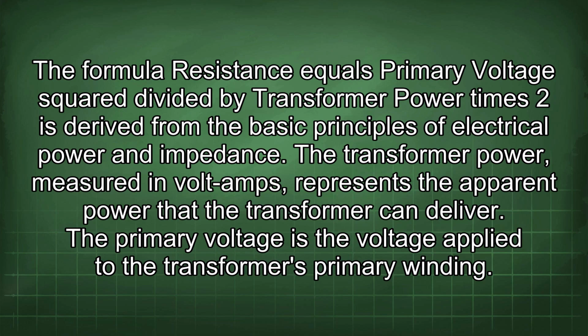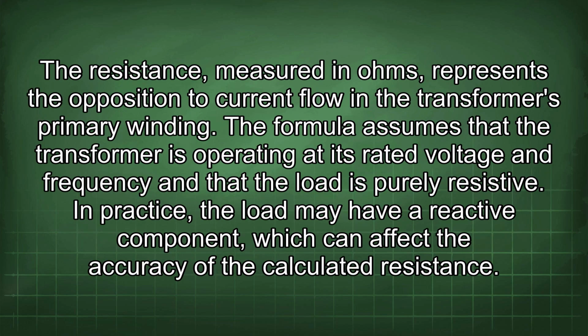The formula resistance equals primary voltage squared divided by transformer power times 2 is derived from the basic principles of electrical power and impedance. The transformer power, measured in volt amps, represents the apparent power that the transformer can deliver. The primary voltage is the voltage applied to the transformer's primary winding. The resistance, measured in ohms, represents the opposition to current flow in the transformer's primary winding.